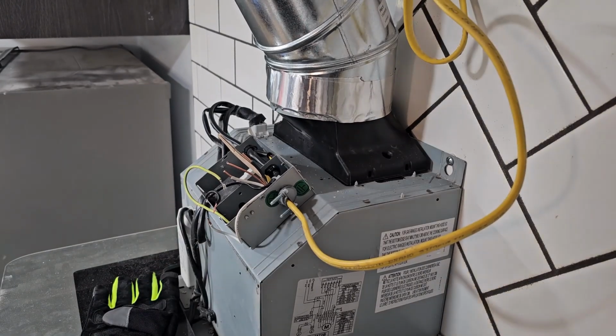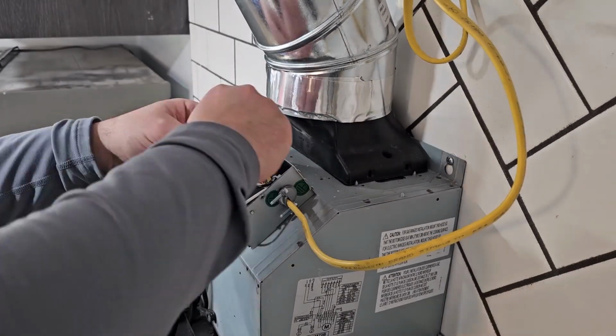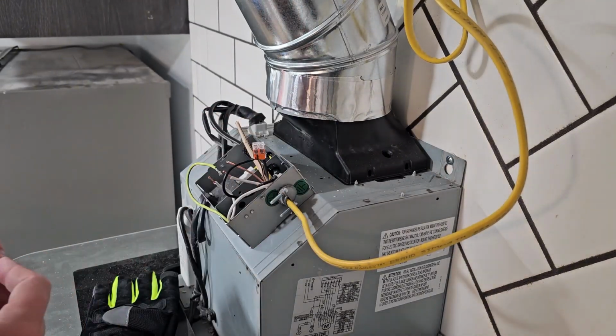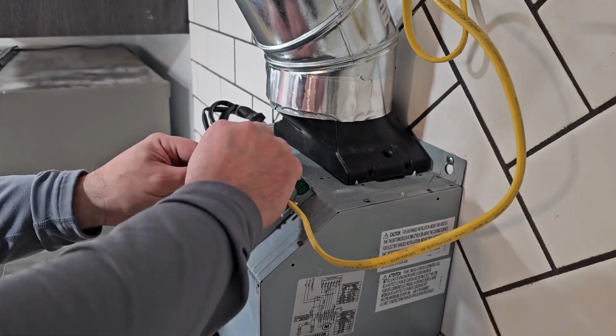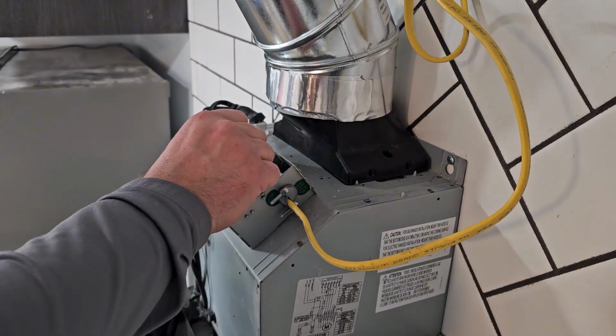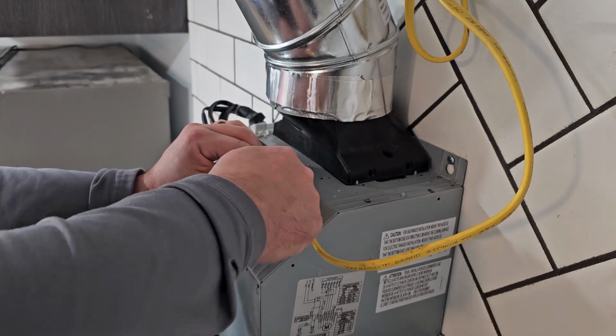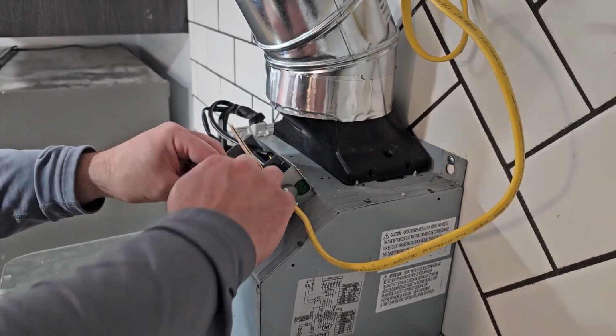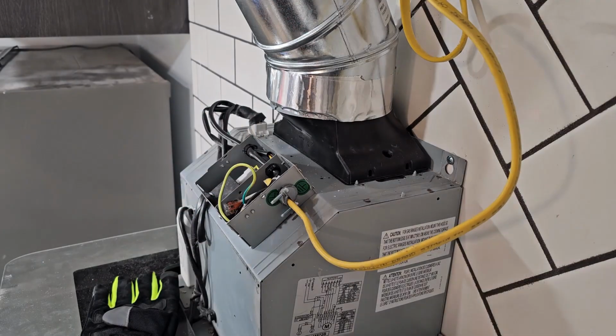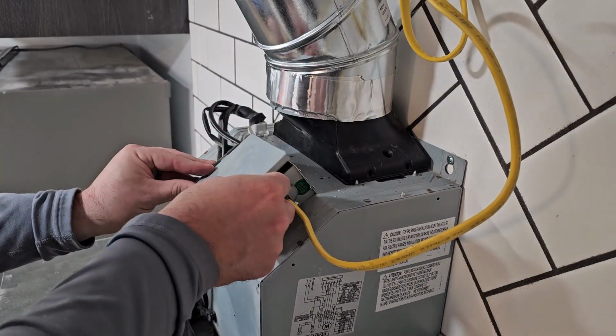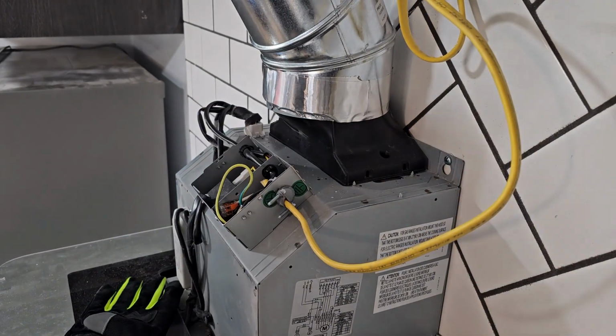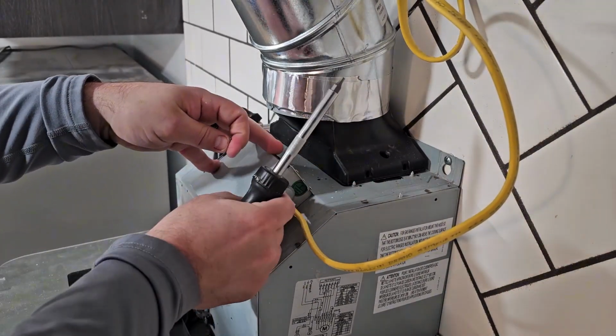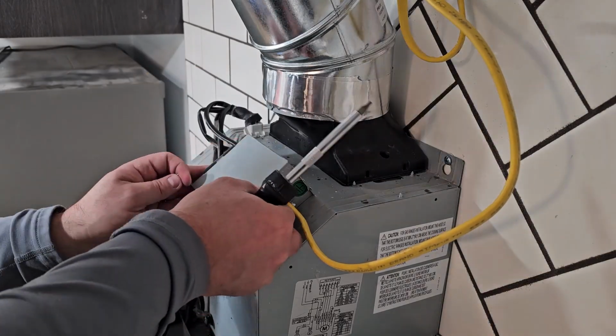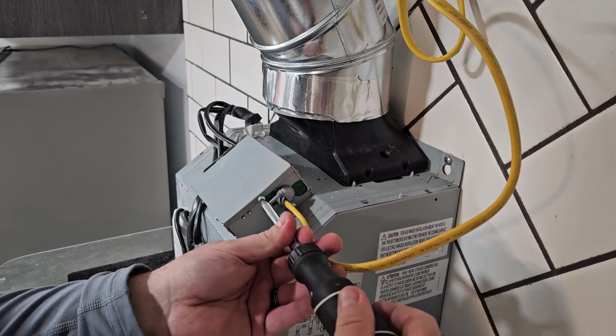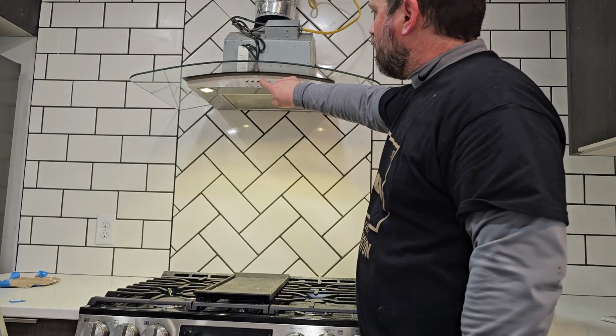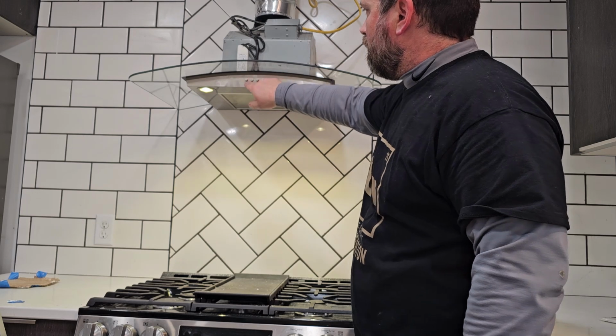In most cases, the wiring should be pretty standard. White to white, black to black, green to bare copper, or bare copper to bare copper. But in some cases you may have different colored wires, so make sure you check with your instructions. Now in most cases I do tend to use a wire nut on my grounds, but you could definitely use another Wago 221 lever nut. Now before I put the cover on, I'm going to go ahead and turn the power back on and test the hood vent out.